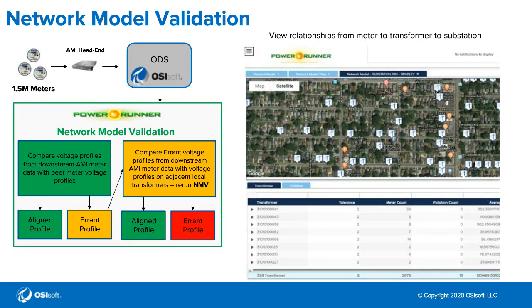Jumping into network model validation: this example uses a GIS feed for the baseline of relationships between assets on the system. We're doing a voltage comparison of the profiles of grouped meters on a particular transformer. Looking at the relationships here, we have about 328 transformers behind this one substation and about 2676 meters, but we found 13 violations on this particular circuit.